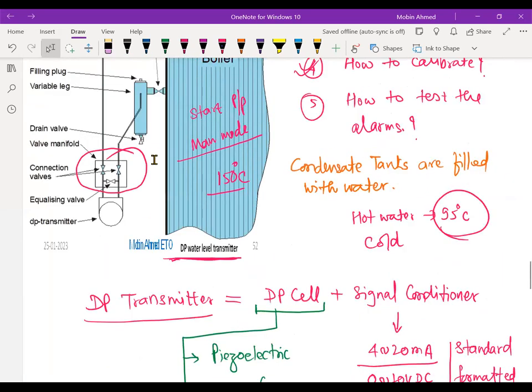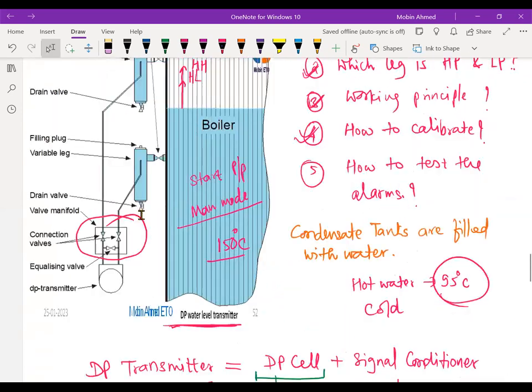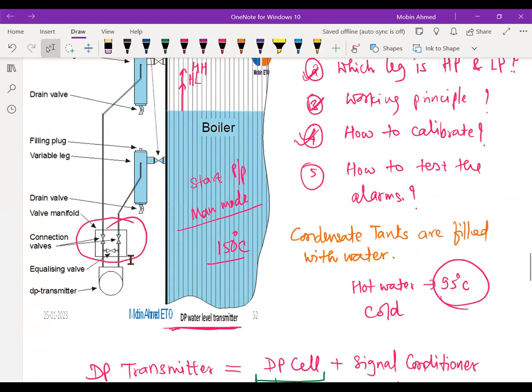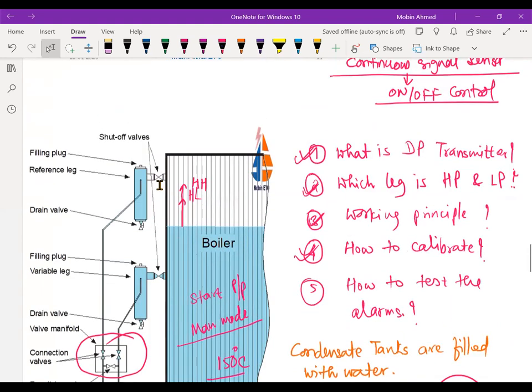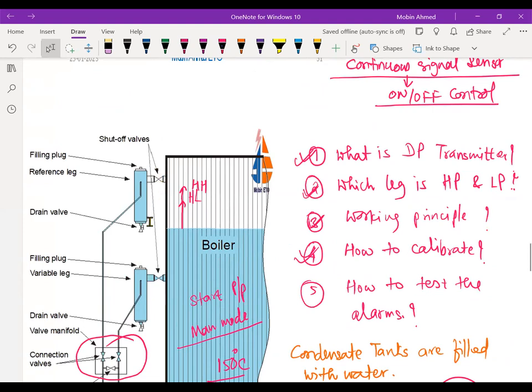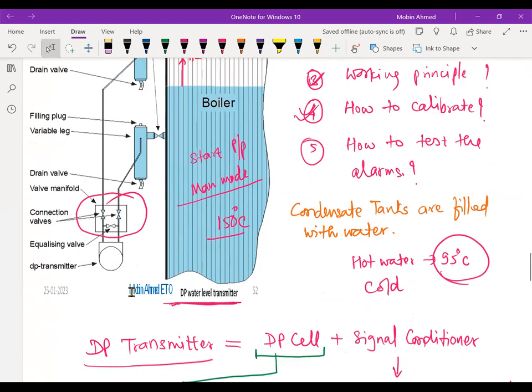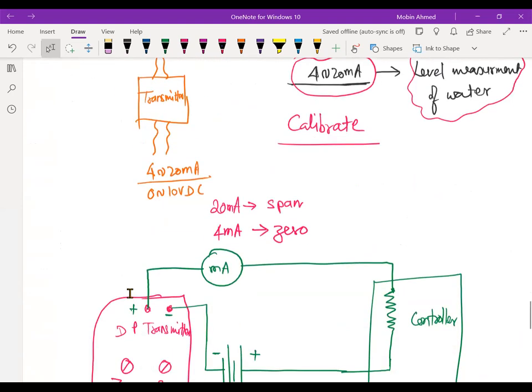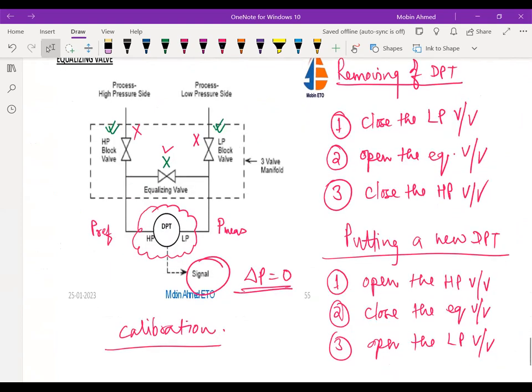Here, what you are doing basically, if you are closing this shut-off valve and when you are going to open here, your steam pressure is out. And this side, still the steam pressure is there. You have not relieved the pressure, because it is closed here. In this case, this will get damaged. Okay. So this is how we are going to do the calibration and service, what the equalizing valve is and all. So this is when we remove and put back the DPT. This is a very important one. This should not leak and do not open it. Otherwise, there will be an error in the signals.